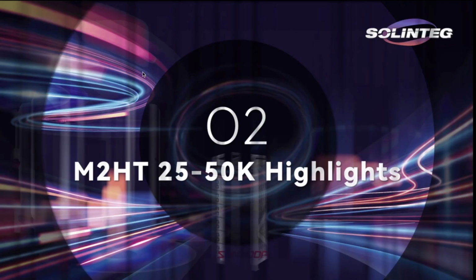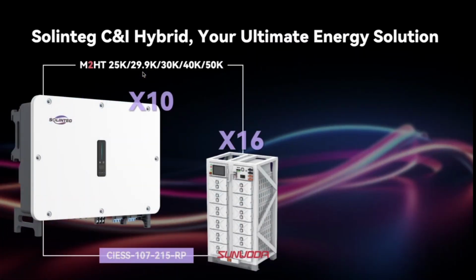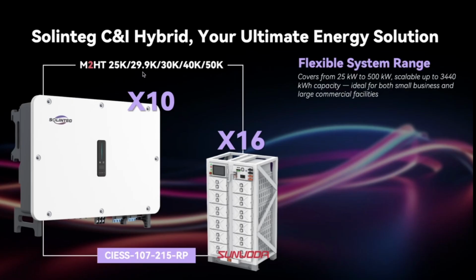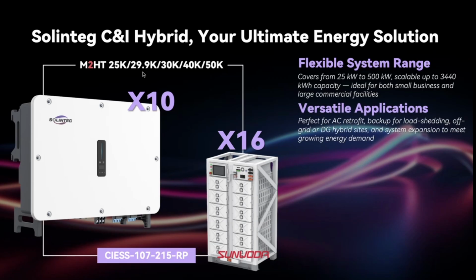Now let's take a look at the overall highlights of our C&I hybrid solution. First, in terms of system flexibility, this inverter offers multiple models ranging from 25 to 50 kilowatts, and through parallel connection, the system can be scaled up to over 500 kilowatts. When paired with Sunwoda's CIESS battery series, the total capacity can reach up to 3.4 megawatt hours, which perfectly fits various applications, from large residential systems like villas to small commercial sites such as farms, retail stores, or even light industrial workshops. Secondly, the system supports multiple scenarios, including AC retrofit, backup for load shedding, on and off-grid switching, and DG hybrid setups, making it an ideal choice for South Africa's diverse energy needs.